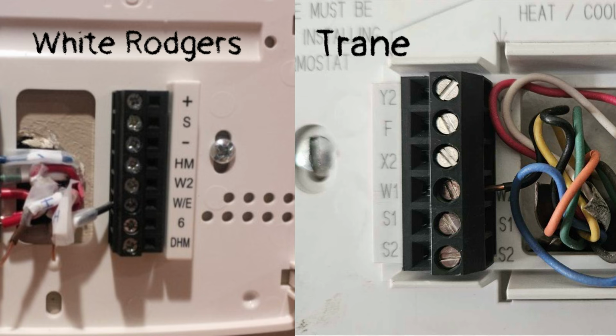One thing you want to keep an eye on when you're upgrading thermostats is that you may have an auxiliary terminal on your old thermostat, but may not see one on the new one. Both of these thermostats, for example, have W2 terminals, but no auxiliary. Both of them use the W2 also as an auxiliary. So they're still a dual terminal, they're just not labeled that way.